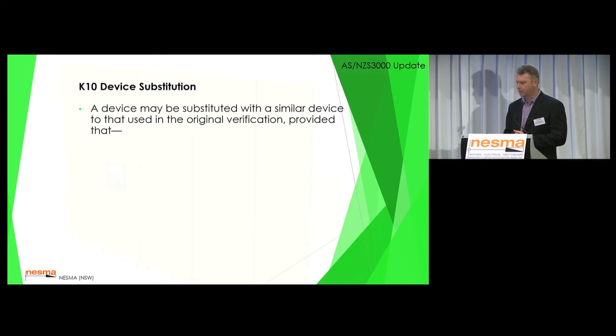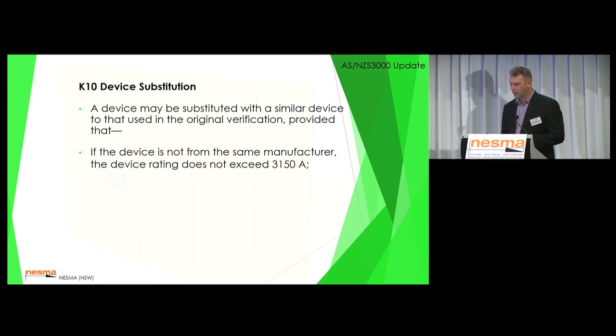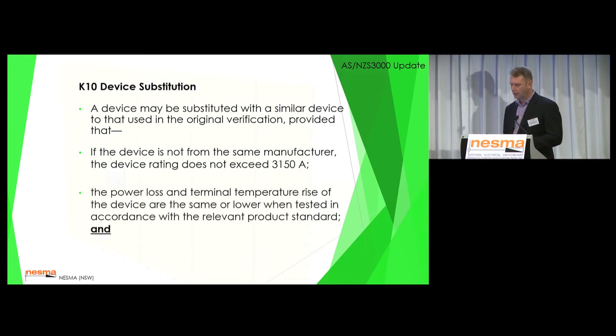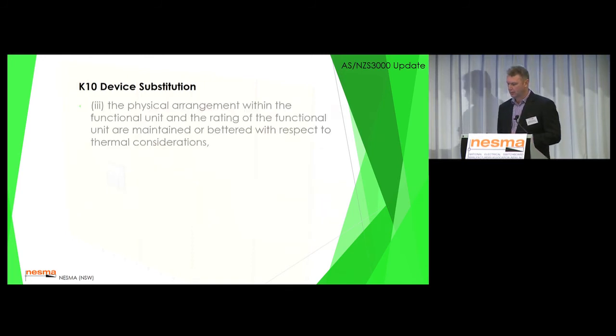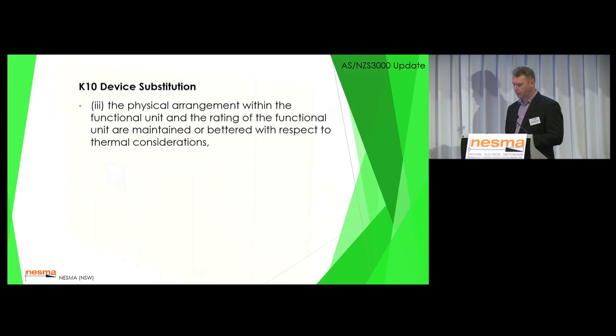A device may be substituted with a similar device that is used in the original verification, provided that if the device is not from the same manufacturer, it does not exceed 3150 amps. So if you're going to go over that rating and do some 4000 amp devices, then basically you have to test. The power loss and terminal temperature rise of the device are the same or lower when tested in accordance with the relevant product standard. So that's one that would have to refer back to the manufacturing data. And the physical arrangement, the functional unit is the same.